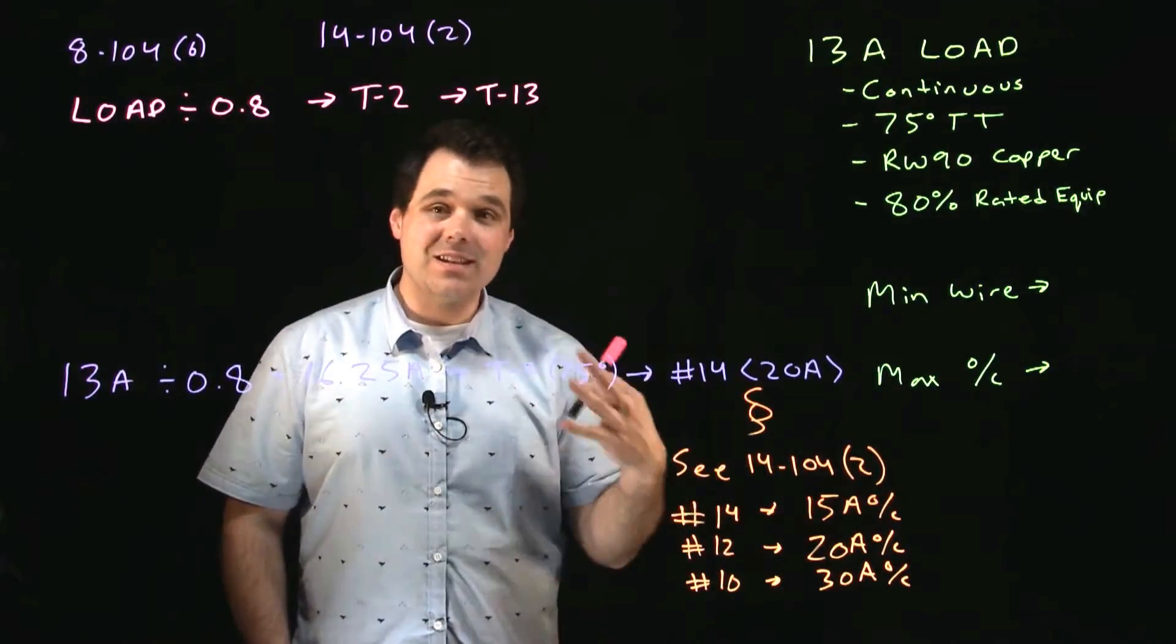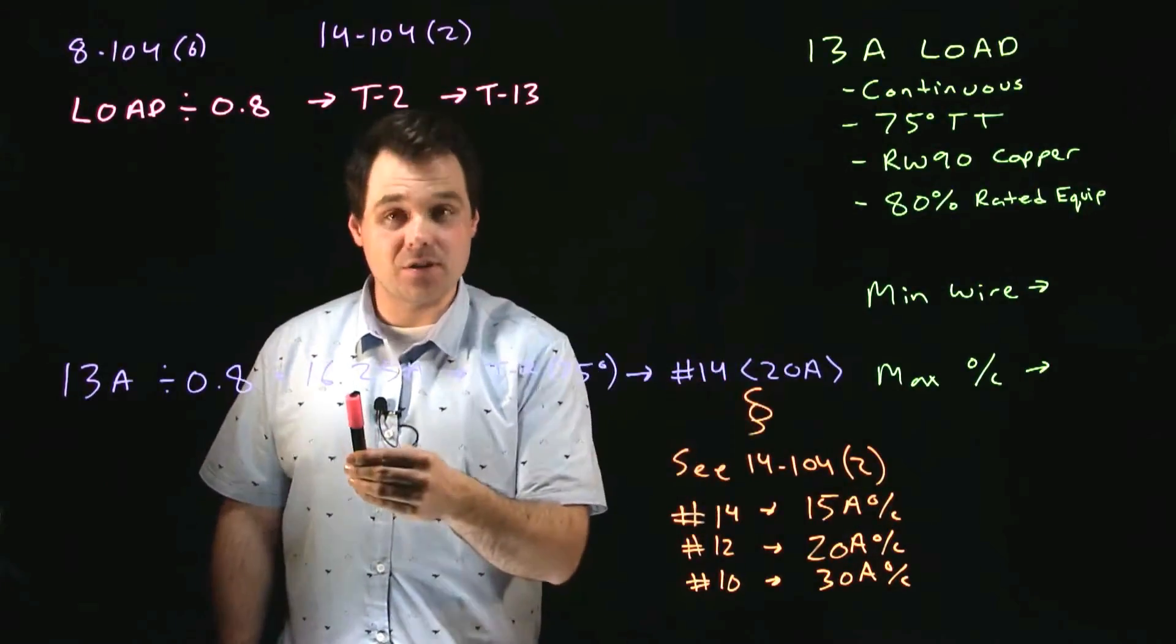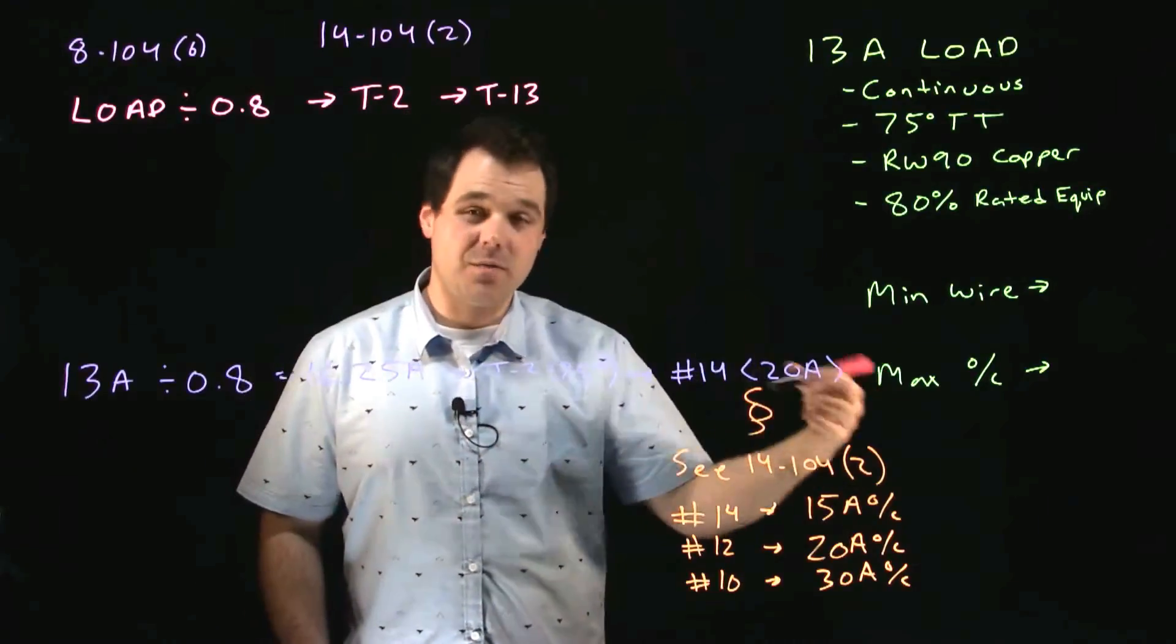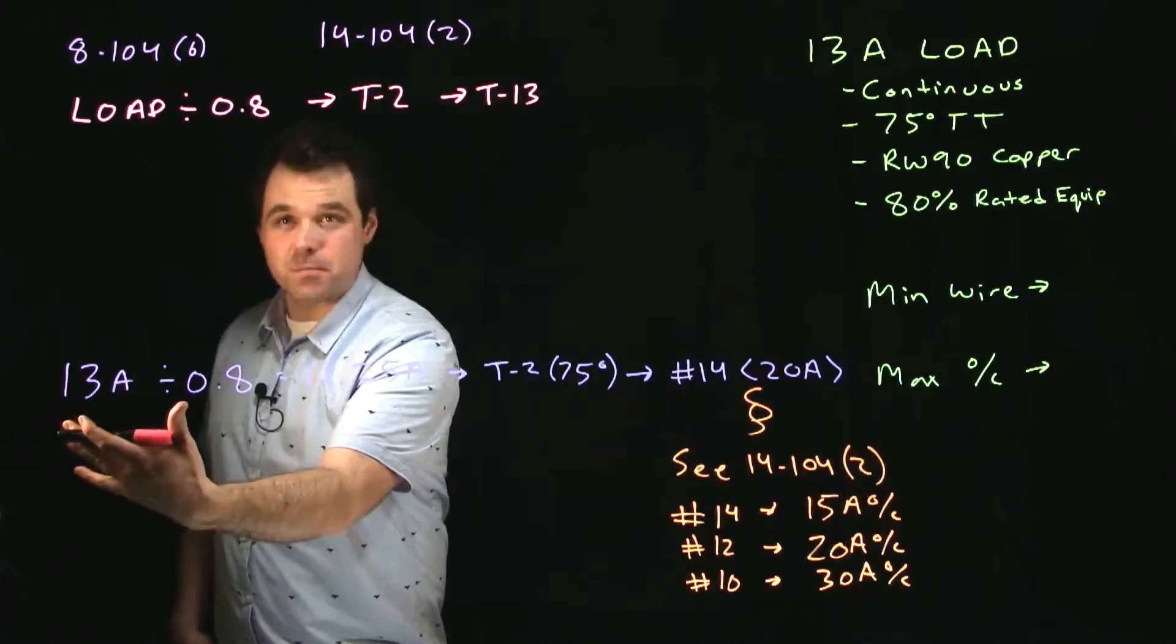Which means in this case we actually need a 20 amp breaker. Because 20 amps would be bigger than the 16.25 and if we got 80% of that 20 amp breaker would be 16 amps which is big enough for my load.